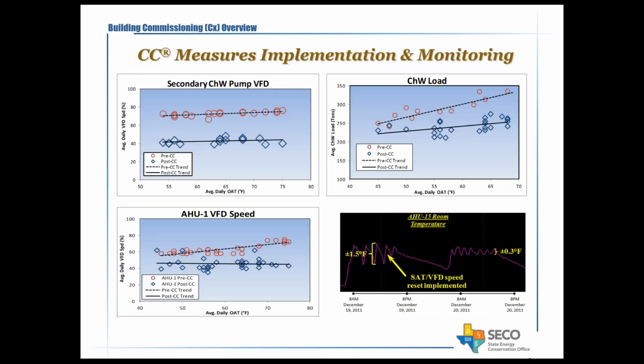Just like existing building commissioning, you want to show the improvements made and the energy savings achieved. For example, on the left side, this is how the chilled water pump with VFD was operating before. When the optimization sequences were implemented, you'll see a drop in the variable speed drives, and the result is energy savings associated with it.